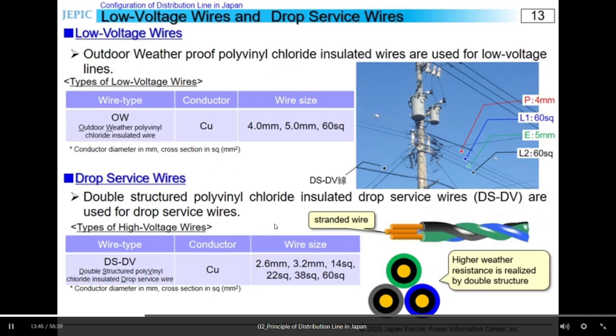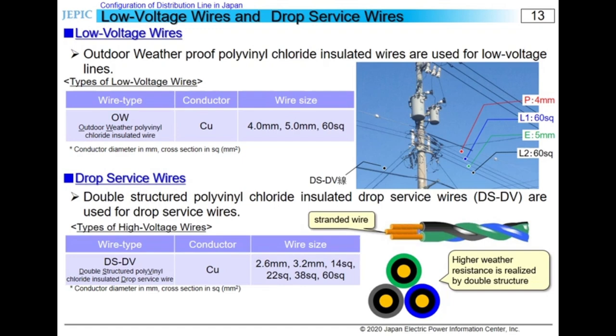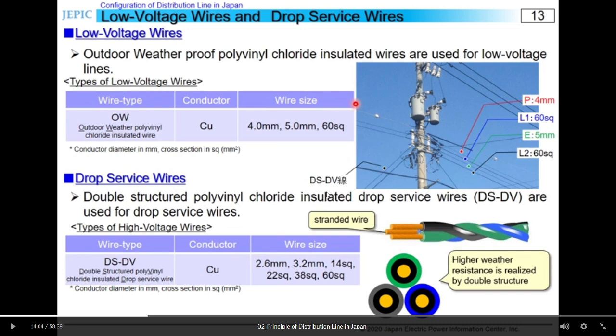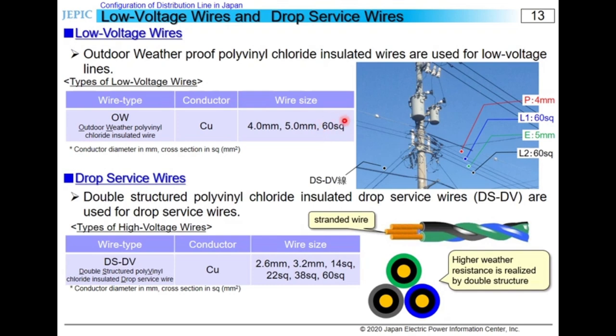In this page, I'll explain about wires used in low voltage lines and drop service lines. As for low voltage line, in Hokuriku area, copper conductors are commonly used, but other electric power companies use aluminum conductors too. As shown in the upper table, wire sizes used as low voltage lines are 4 mm, 5 mm of single wire, and 60 square stranded wire. The picture is an example of how the low voltage line is installed.